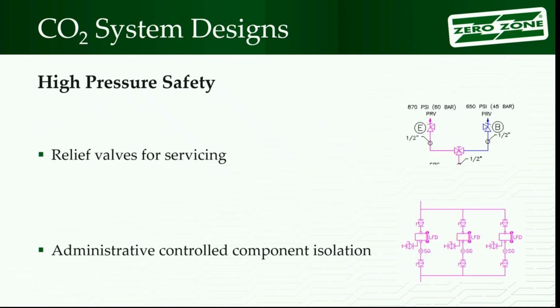Another technique used to improve serviceability in the system is to have two different pressure relief valves on the same system. These are both fire rated valves, so it's not a regulating relief. What it is for is service. So the liquid line going out to the system is rated at 650 psi. During normal operation, I want that three-way valve open so that 650 psi is protecting those lines. If I'm doing a service activity, I know the system's going to be down, there's some maintenance project we're doing, repiping, the power company said we've got to shut you down for whatever. You know it's going to be down for maintenance.